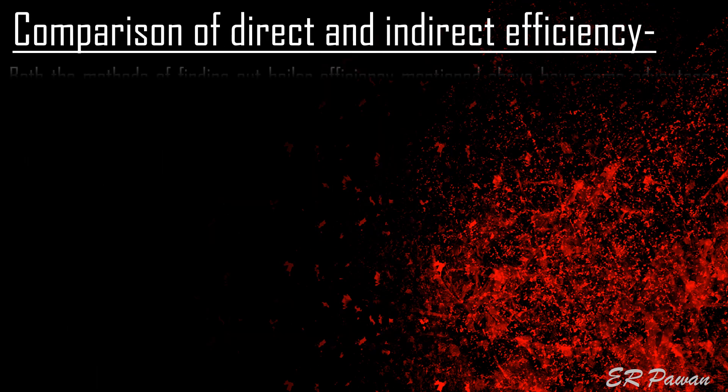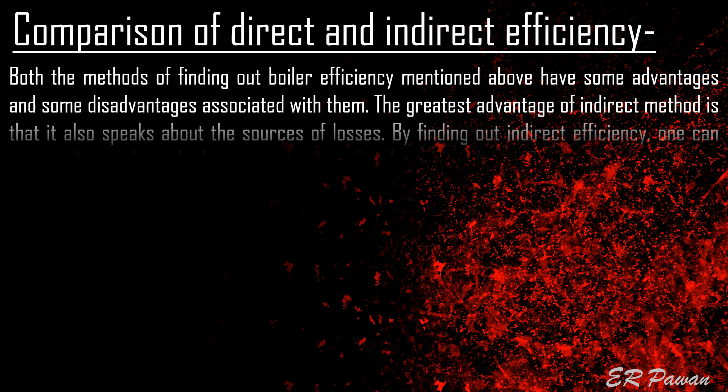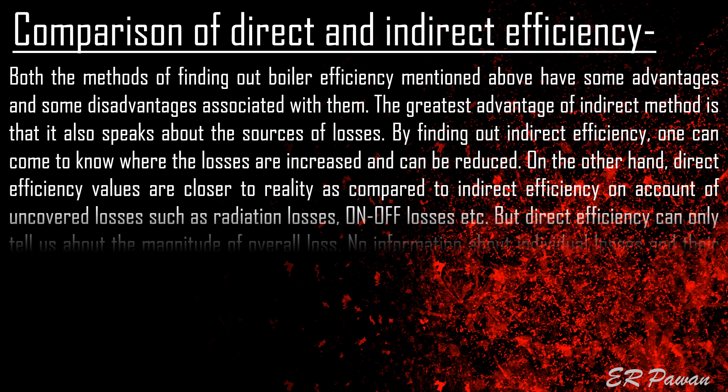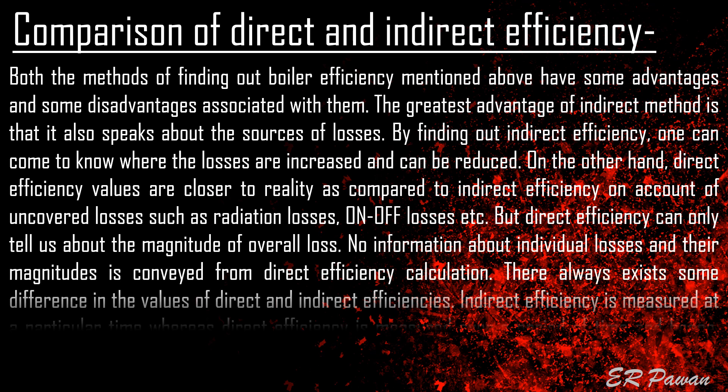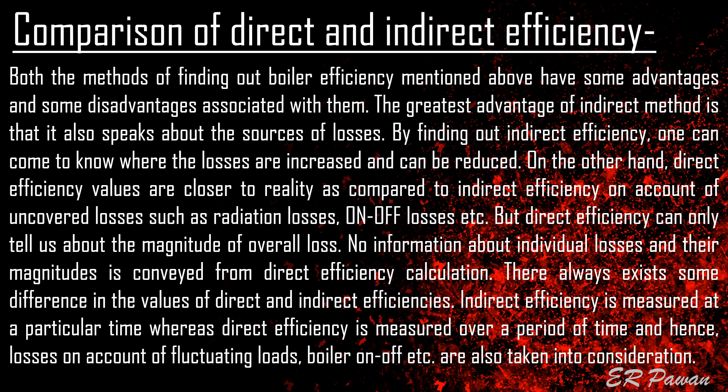Both methods of finding boiler efficiency have advantages and disadvantages. The greatest advantage of the indirect method is that it also identifies the sources of losses — one can know where losses are increased and can be reduced. On the other hand, direct efficiency values are closer to reality as they account for uncovered losses such as radiation losses and on-off losses, but direct efficiency can only tell us the magnitude of overall loss with no information about individual losses. Indirect efficiency is measured at a particular point in time, whereas direct efficiency is measured over a period of time, so losses due to fluctuating loads and boiler on-off cycling are also taken into consideration.